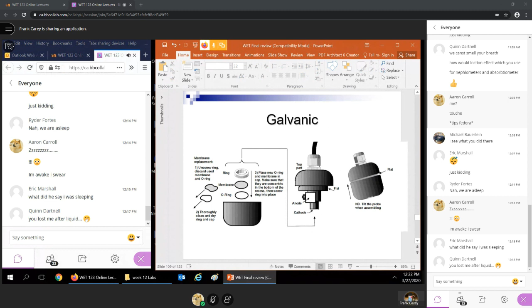Galvanic versus polarographic: know that the polarographic require voltage or current, while the galvanic give out a voltage or current. Polarographic are bad in every way - they require more calibration, longer time to warm up, whereas the galvanic require less time to warm up and less calibration. But the best by far are the optical dissolved oxygen probes.